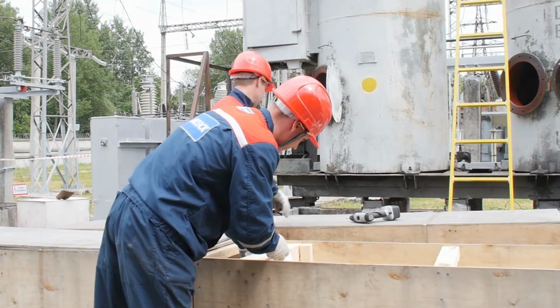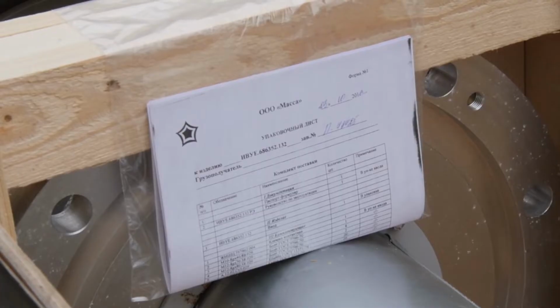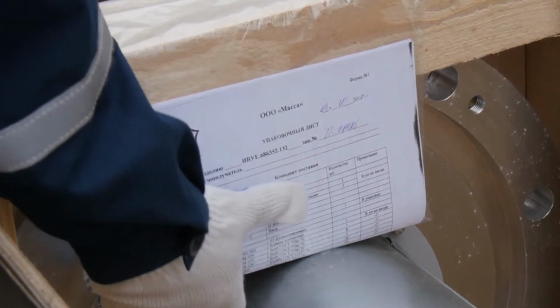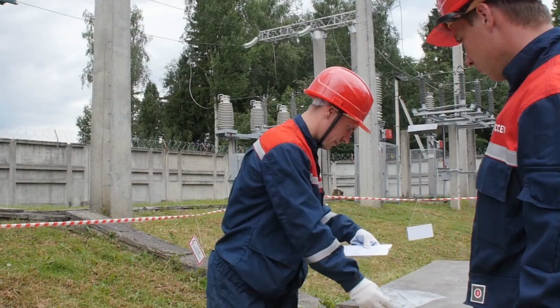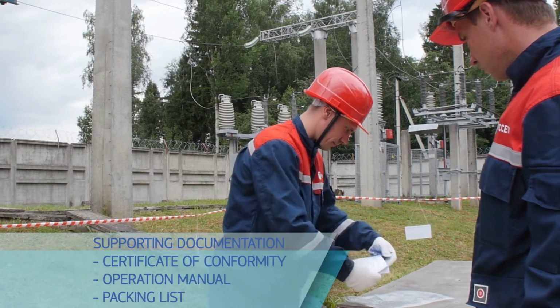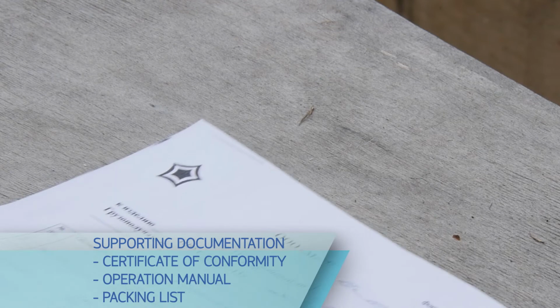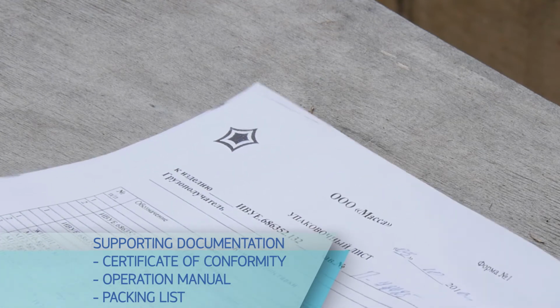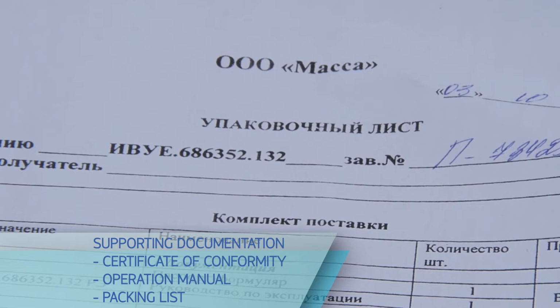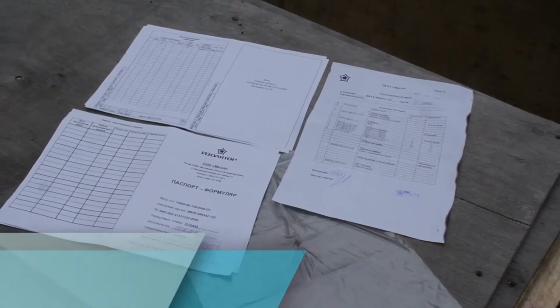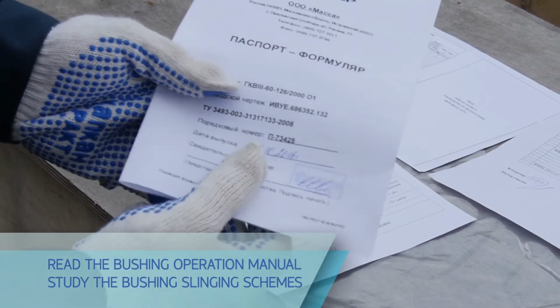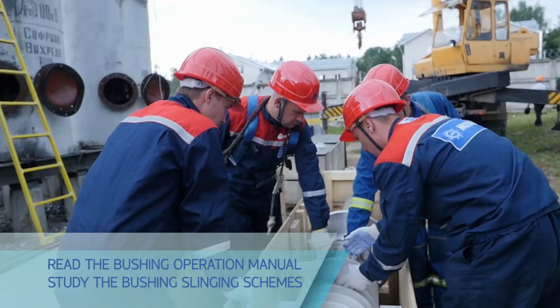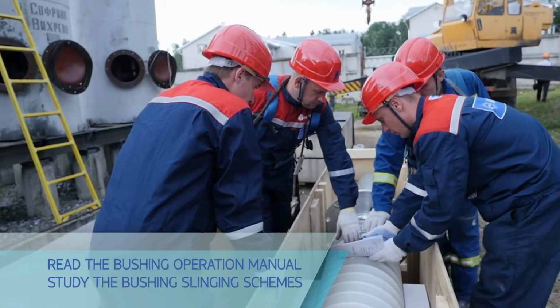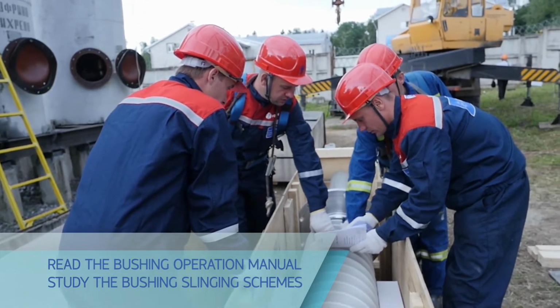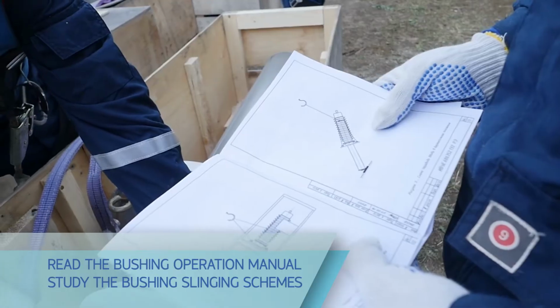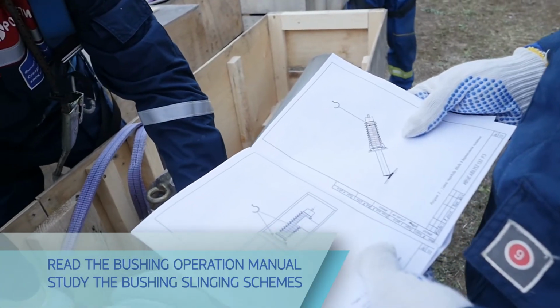Check for supporting documentation attached to the sideboard of the package. The documentation set includes Certificate of Conformity, Operation Manual, Packing List. Check the bushing completeness against the packing list. Carefully read the bushing operation manual. It describes main procedures of bushing unpacking, installation on a circuit breaker, and in-service maintenance. The manufacturer warranties reliable and failure-free operation of the bushing within the entire service life only if all the instructions of the operation manual are met.